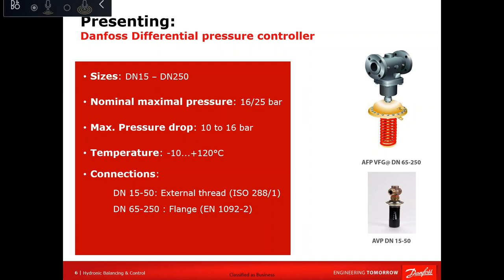So if you take one branch, if the tenant will be installing normal two-way valves and you are putting a PICV or an autoflow limiter on the return, the total flow will be limited. But how this flow is distributed between the units inside, you will not know. The DPCV will fix a certain differential pressure value that will be applied to the whole shop. So whether the tenant uses two-way valves or PICVs, the building owner side is protected, which means regardless of what the tenant is using, he will never see more than the set value that you are putting on the DPCV.